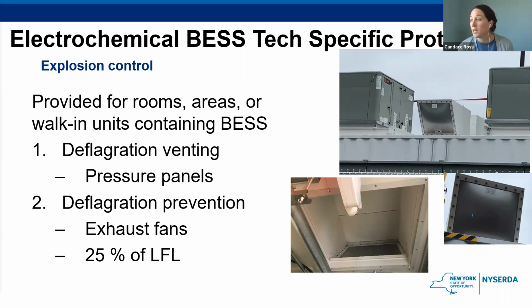This is that same system that's located downstate. So they have the panels on top of the container, and if there was some sort of an event, those would blow open and it would just go up. It would not affect any of the fire department's operations. And they had actually worked with the FDNY to make sure that was in compliance for them as well.